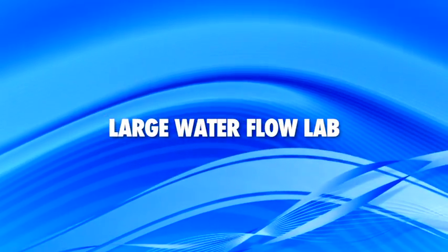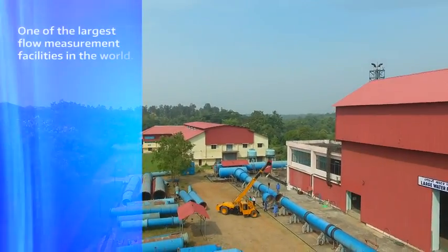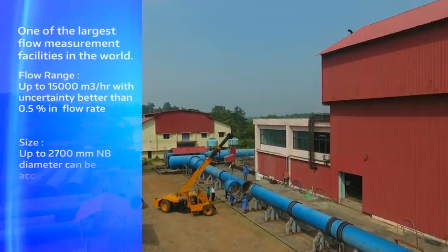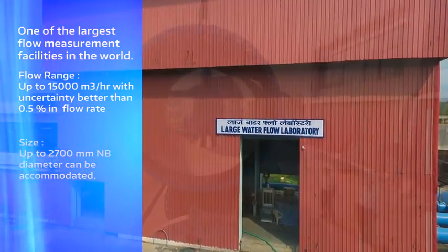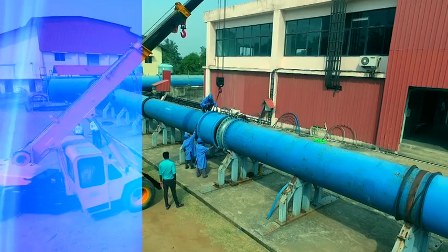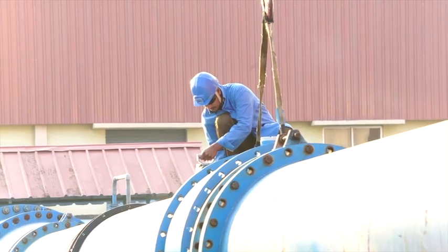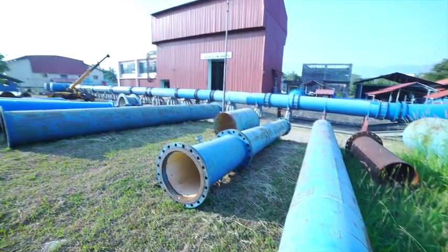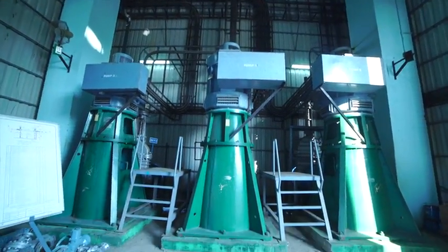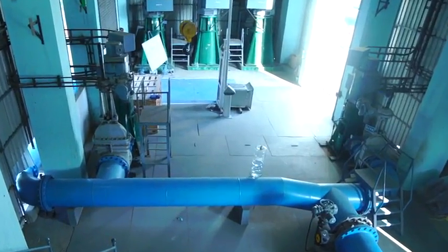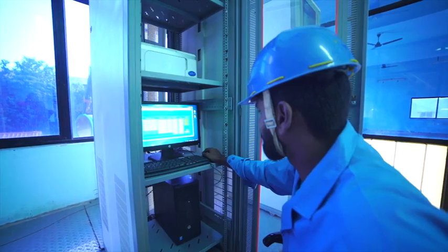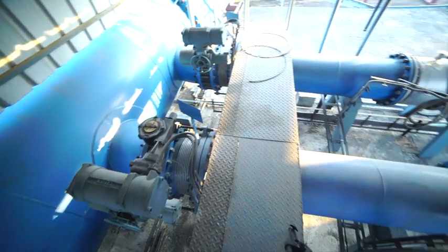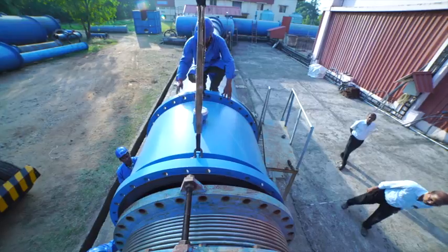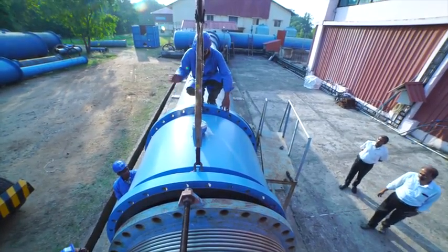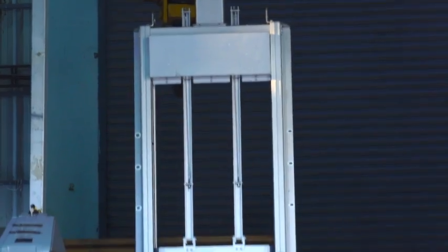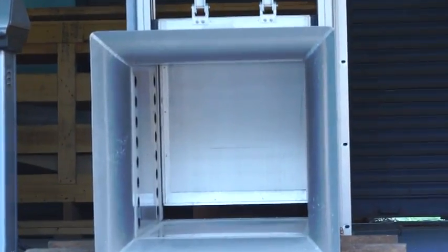The unique large water flow lab at FCRI is one of the largest flow measurement facilities in the world. It was set up in 2012 for meeting the demand of manufacturers and end users for testing large size flow meters and control valves with high accuracy. The facility, with a flow range of up to 15,000 cubic meter per hour with uncertainty better than 0.5% in flow rate, can accommodate pipe sizes up to 2,700 mm diameter. Besides calibration of large diameter flow meters, the facility also tests valves and pumps.